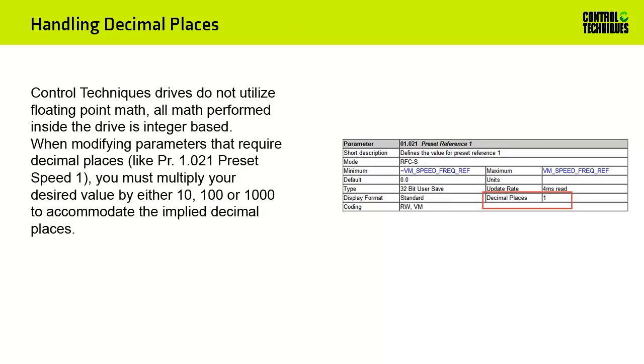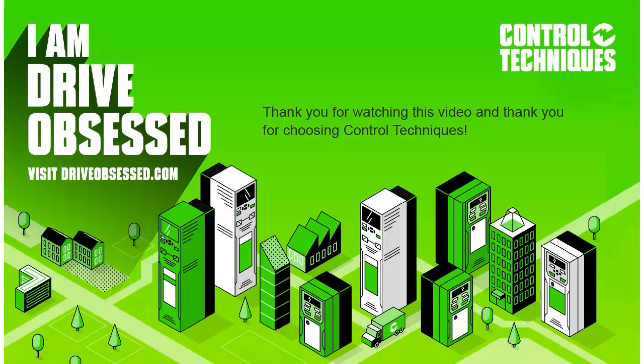Control Techniques drives do not utilize floating-point math; all math performed inside the drive is integer-based. When modifying parameters that require decimal places, like menu 1, parameter 21, you must multiply your desired value by either 10, 100, or 1000 to accommodate the implied decimal places. For example, if I wish to set the preset speed to 100, I would send the number 1000, which will result in the value of 100.0 as my preset speed. Thank you for watching this video, and as always, thank you for choosing Control Techniques.